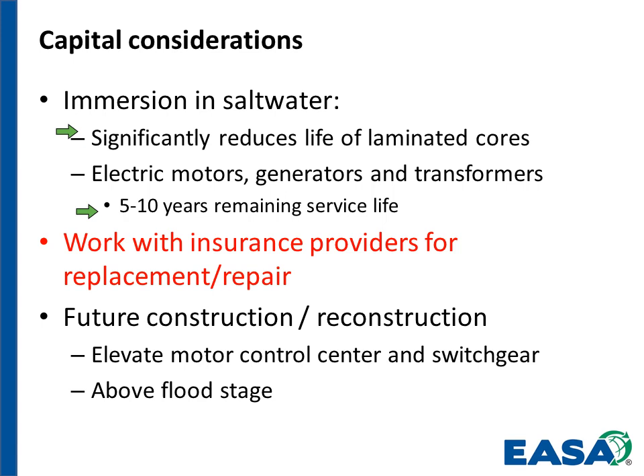So these motors are going to rust and continue to rust if they're immersed in salt water. The same's not true if it's fresh water. So if it's a rain event and it's not a mixture of salt water and fresh water, then cleaning, processing, getting back into service, you should be in good shape. But if it's a saltwater event, a high tidal surge, for example, then a lot of the equipment, and some of it's quite expensive, will need to be replaced within about a 5 to 10 year period.